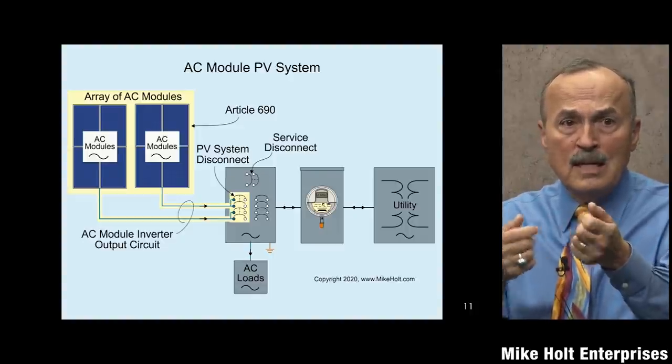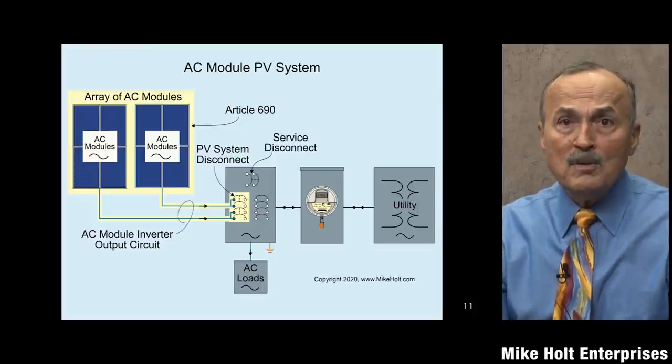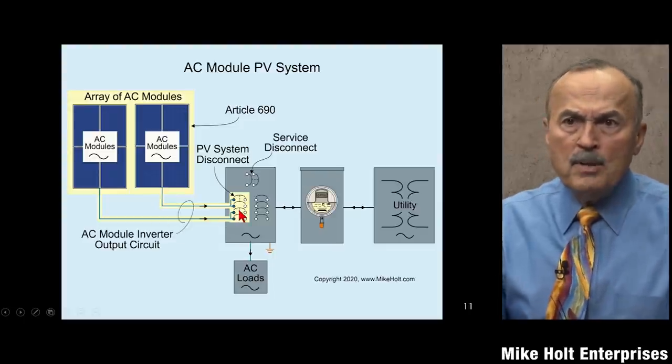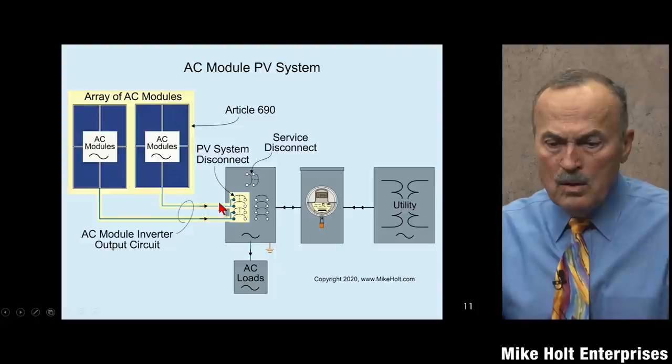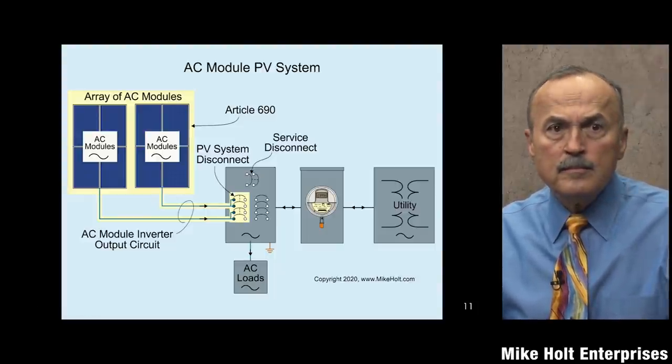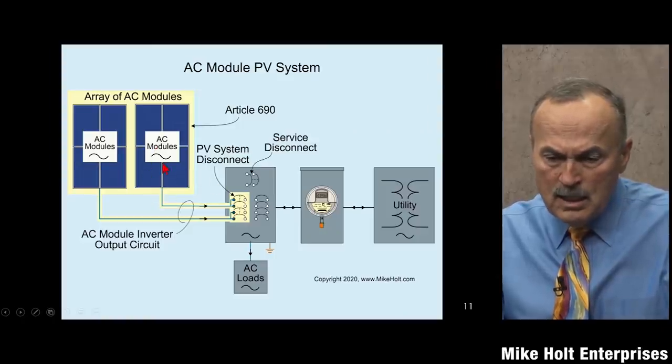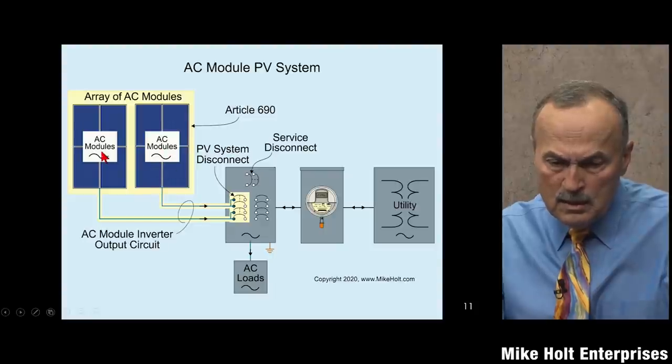With AC modules, you've removed a whole bunch of Article 690 code rules. The only part of Article 690 that would apply is the inverter output circuit conductors. You follow the manufacturer's instructions for breaker sizing, and for all practical purposes it's plug-and-play. The modules look like regular panels - you wouldn't even know unless you flipped one over. We'll show a picture when we talk about definitions.